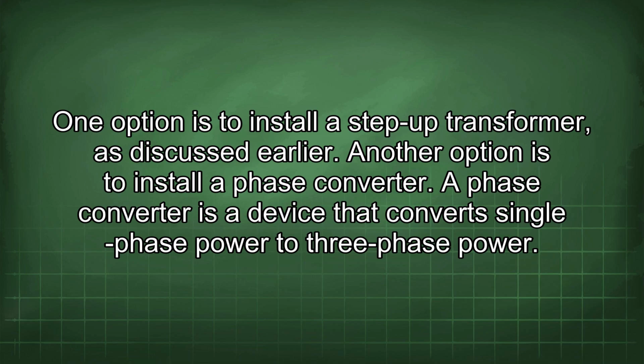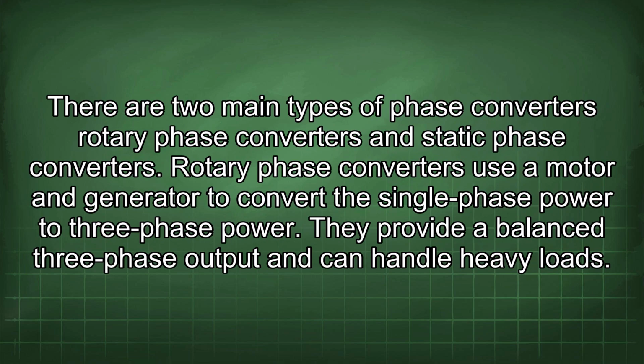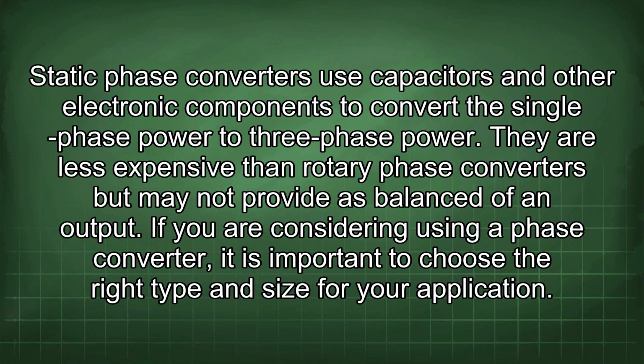Another option is to install a phase converter. A phase converter is a device that converts single-phase power to three-phase power. There are two main types of phase converters: rotary phase converters and static phase converters. Rotary phase converters use a motor and generator to convert the single-phase power to three-phase power. They provide a balanced three-phase output and can handle heavy loads. Static phase converters use capacitors and other electronic components to convert the single-phase power to three-phase power. They are less expensive than rotary phase converters but may not provide as balanced an output.